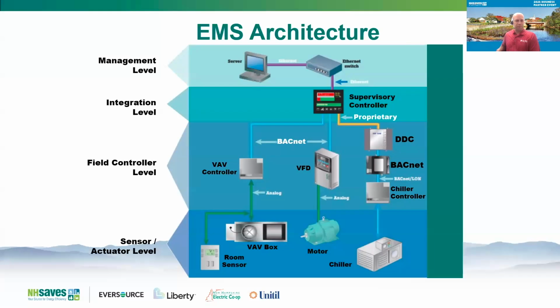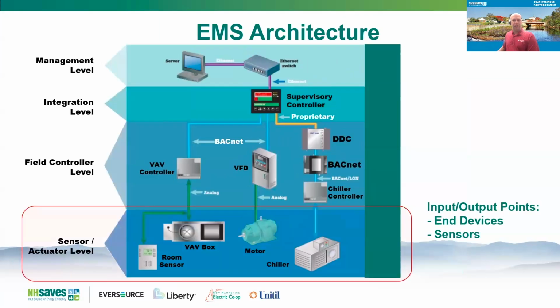and do a sort of a bottoms up approach, starting at the end device, if you will, or the sensors. So the lowest level of a BMS architecture is the sensor or actuator level. This is where you're going to have sensors in the space, such as a room temperature sensor or a relative humidity sensor that provides feedback to, say, a VAV box, where the VAV box is going to modulate the damper and/or reheat to maintain that space temperature that's being measured with that sensor.